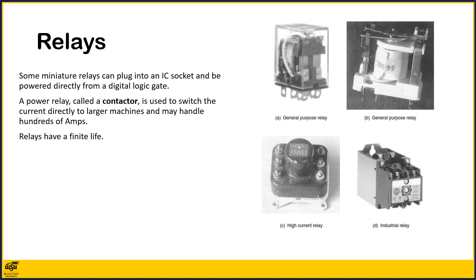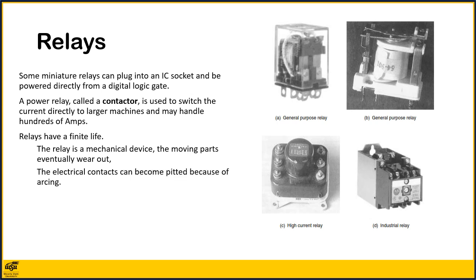It is well to remember that for two reasons relays have a finite life. First, because the relay is a mechanical device, the moving parts eventually wear out. And second, the electrical contacts can become pitted because of arcing. The contact wear is very dependent on the electric current that is being switched. For example, a certain relay is rated for 9 million operations at 1.5 amps, but only 2 million operations at 3 amps. 2 million operations sounds like a lot, but if this relay were in a 24-hour factory being used in a repetitive operation every 10 seconds, it would have to be replaced every 8 months.